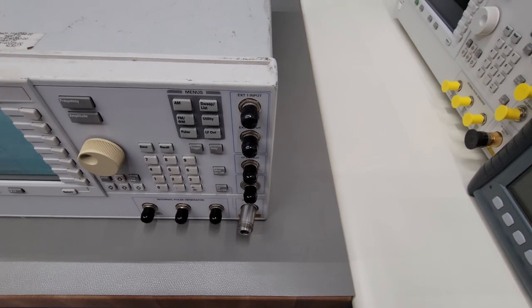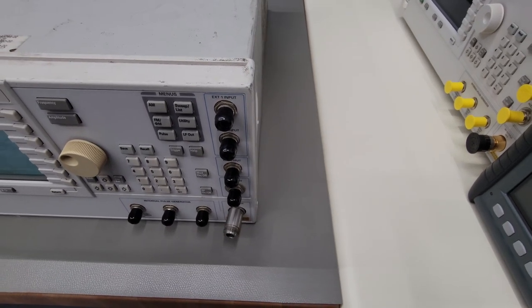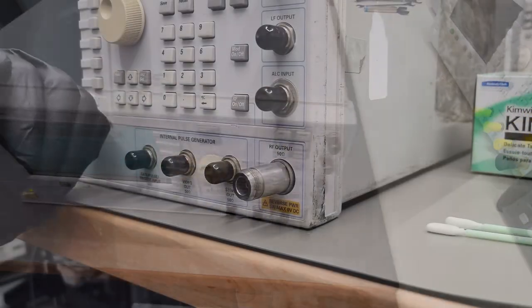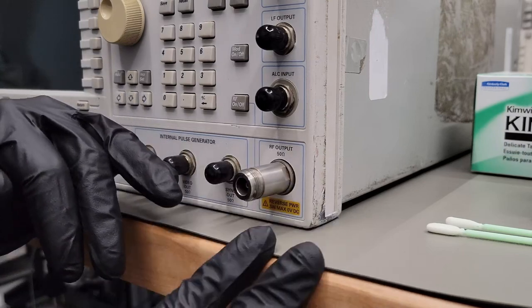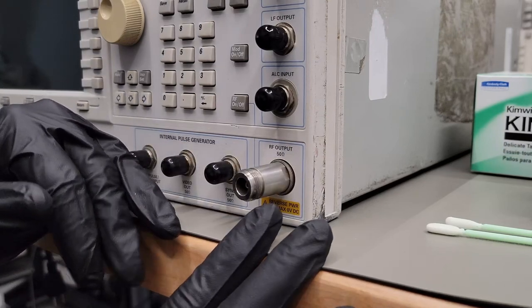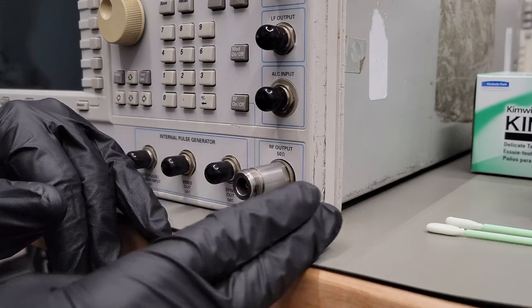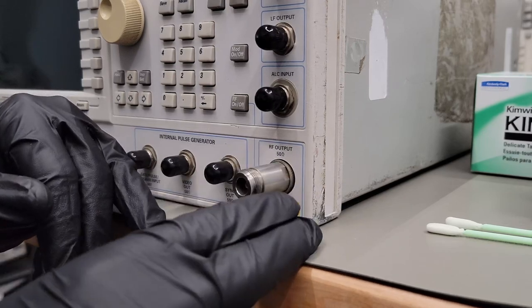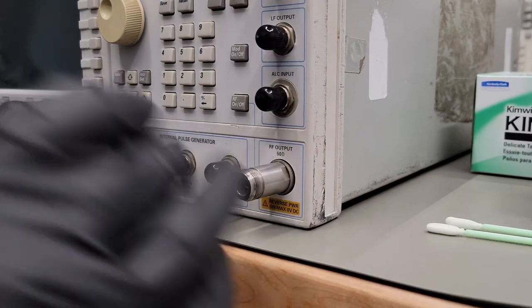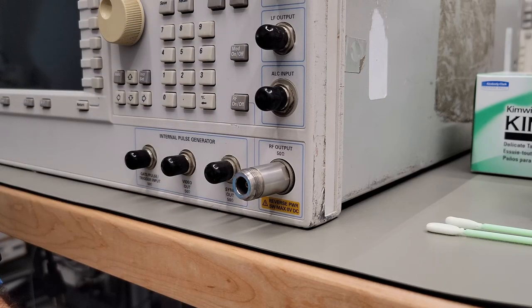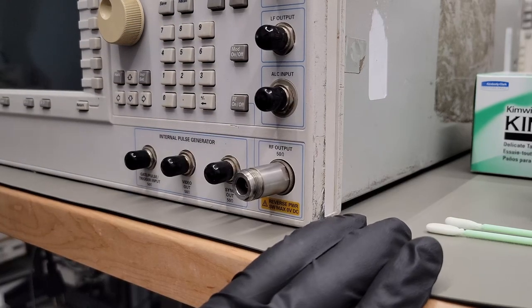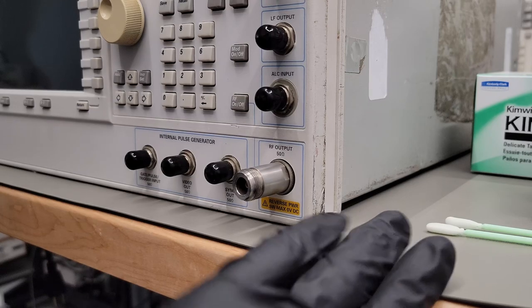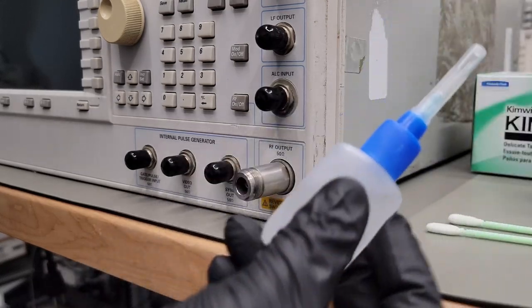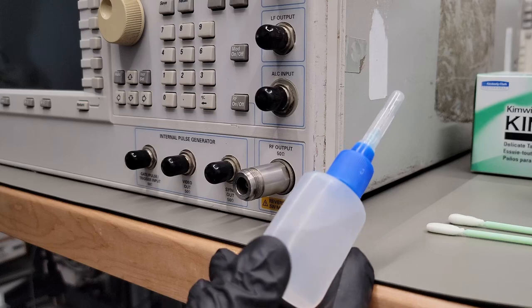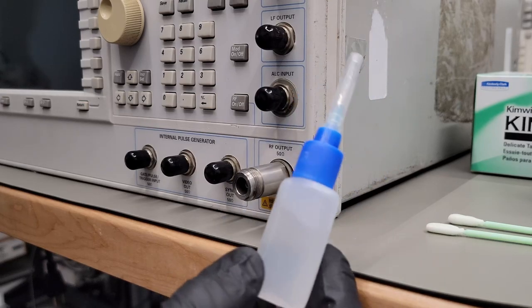And I'll show you my process for cleaning microwave connectors like this safely. One thing to know and always respect about this process is that the input could very well be static sensitive, and most of the time it is. So you really want to be careful, always wear your wrist strap, work in a static safe environment. And the only cleaning solution we're going to use is 99.9% reagent grade isopropyl alcohol.